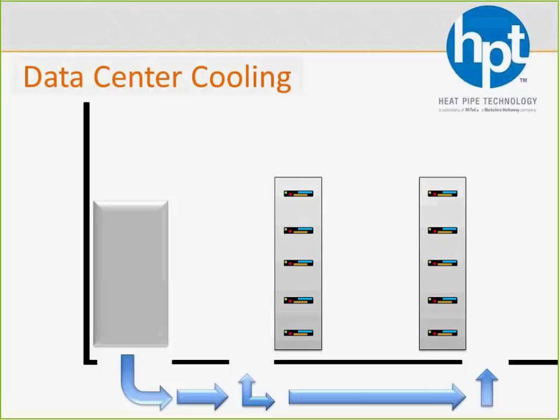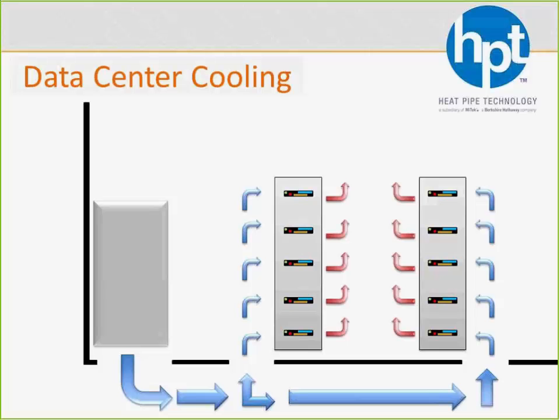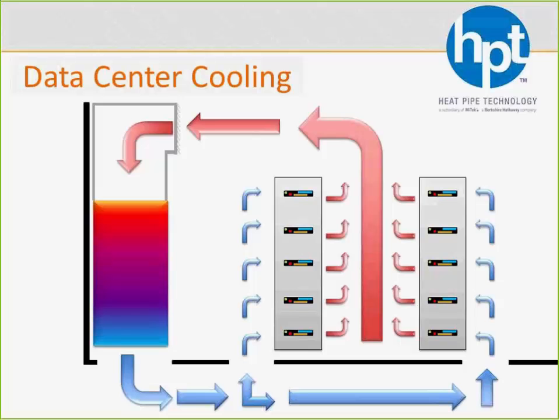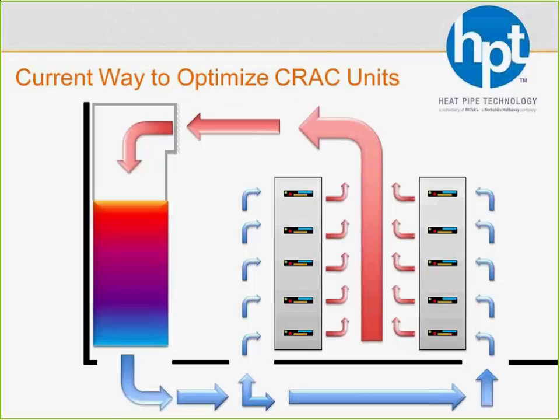They're typically feeding cool air under the floor, and that cool air is going to cool all those stacks that are giving off all that heat. Heat's naturally going to rise. So we're going to cool those stacks, heat's going to rise, and then of course all that hot return air goes right back to the CRAC unit, gets cooled, and the whole system repeats.